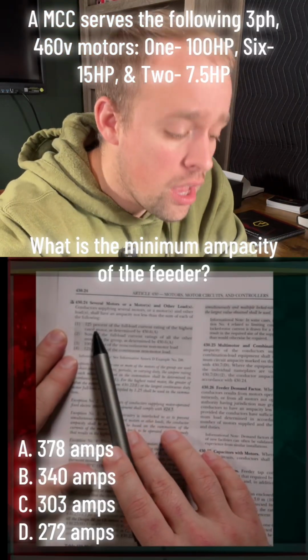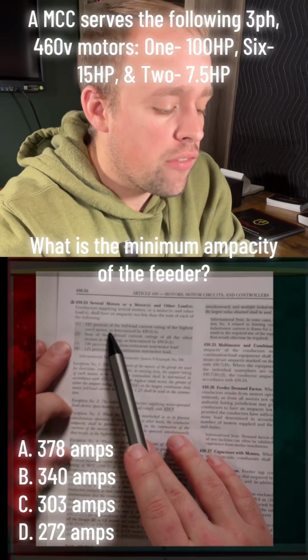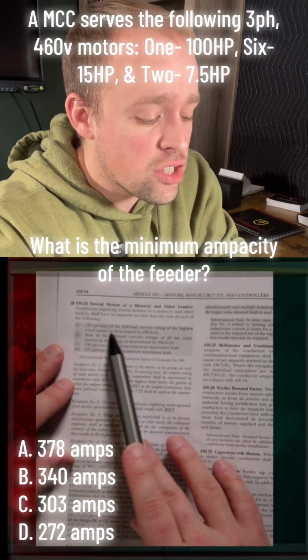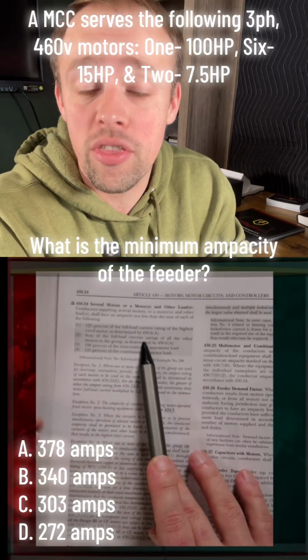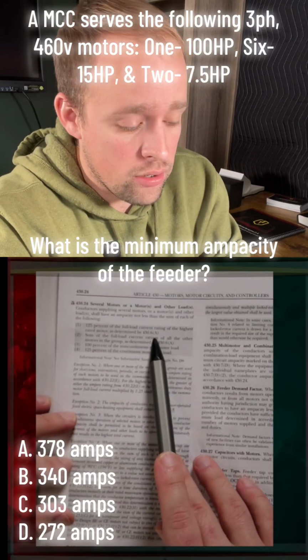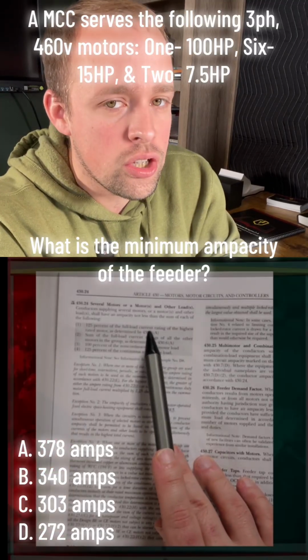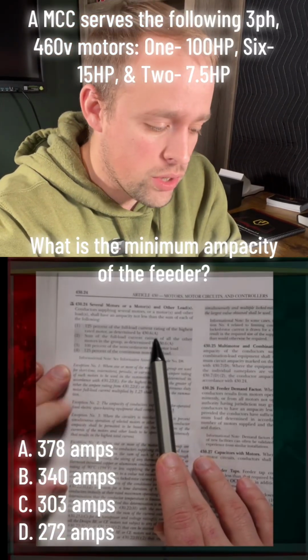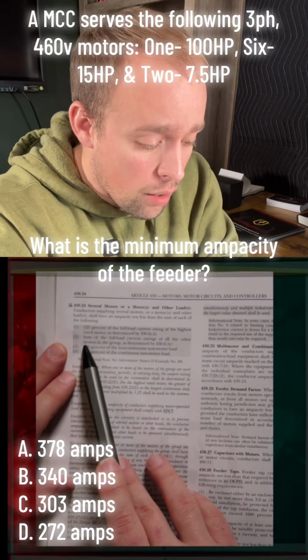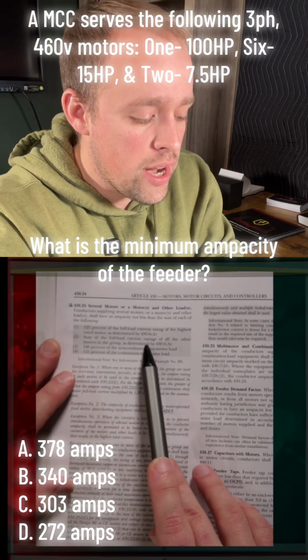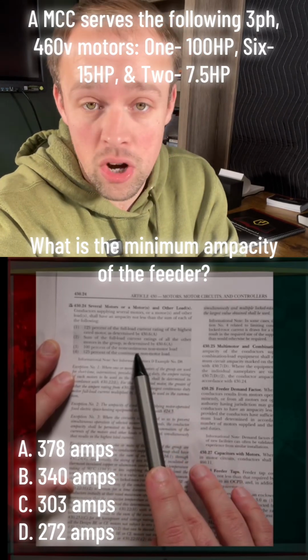So the first one says 125% of the full load current rating of the highest rated motor as determined by 430.6(A). So I'll probably explain that code article to you, but I do encourage you to read that on your own time. 2 says the sum of the full load current ratings of all other motors in the group as determined by 430.6(A).